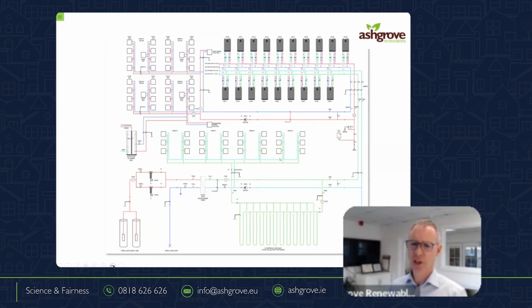And we would have a preference then, because of efficiency or maybe something else. If the load drops from 500 kilowatts, for whatever reason, what do we want to continue doing? It might be more efficient to take the waste energy from the waste air because it's hotter and our COP is higher. And then our ground loop might be the next and last. The ground loops, typically the running cost of those pumps would make that decision for us. That would be the one we would turn on last normally. And that's only an example.